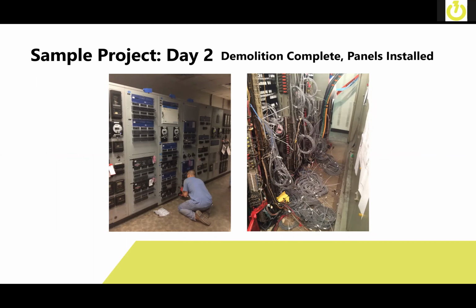Day two, basically, we got everything completely demolished at the customer's facility. On the left-hand side, you can see the new panels are fully installed. They have the blue tape above, what we used to identify which panels we were working on, just to make sure that we didn't get into a situation where we were working on something we weren't supposed to. And as you can see, we basically covered up the entire front faceplate with the exception of some meters and existing equipment that the customer didn't want to be removed due to issues with the transmission crew and how they meter in the facility. And in the back, you can see the kind of wire whips that we have. Day number two, I usually say it looks like a bunch of spaghetti on the inside. Doesn't really look that nice, but once we get done, you'll see a final picture and you'll be able to see the final quality.